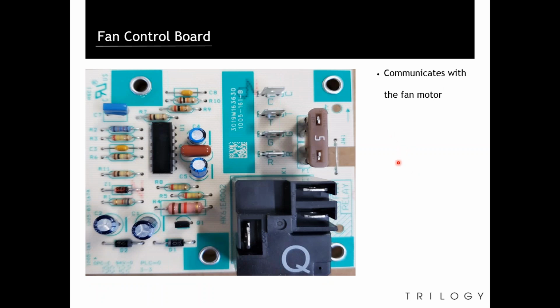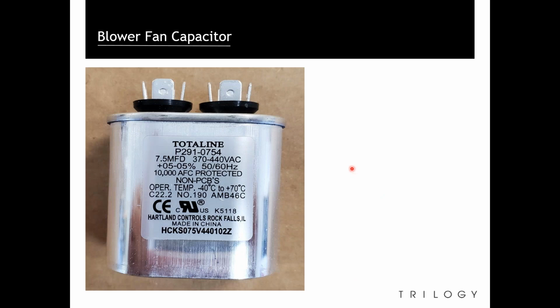Our fan control board communicates with the fan motors. High speed, medium speed, low speeds, that is the job of the fan control board. Our blower fan capacitor, again, adds the power to get the fan motor started.